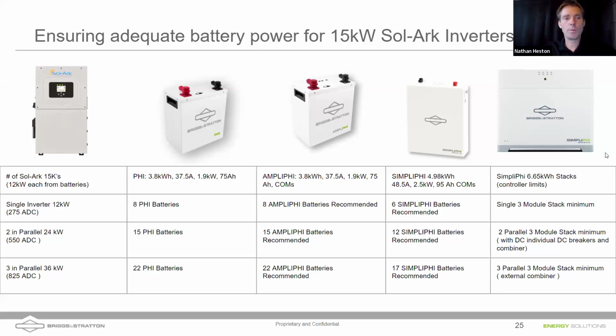I'll skip through this slide quickly, but keep in mind that if you're using batteries to power an inverter, you want to make sure the output power capability of your battery is sufficient to meet the demands of the inverter. All batteries have a limitation based on their C rate, and that C rate output may or may not be big enough. We're showing you some examples of the minimum recommended battery size to power a Sol-Ark inverter. If you've got a communicating battery like the one on the right, it can tell the inverter to reduce its overall output, but you're sacrificing some of the ability of your inverter if you don't meet the minimum number of batteries shown on screen.